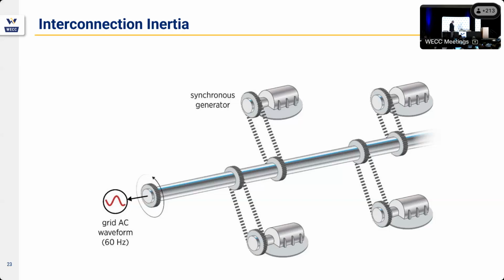This is a great benefit to reliability because what it gives you is time, and that's one of the things we don't have a lot of in interconnected operations. You've all heard that electricity is that one commodity that has to be generated the instant it's demanded. You turn on a light switch, somebody's got to make that electron. One of the great things about inertia is it converts rotating mass to electricity, to megawatts. So the more inertia you have, the more resistant to change in speed, and the more resilient your system. We always care about minimum inertia levels in any interconnection. You can't have too much, too much inertia is a great thing.